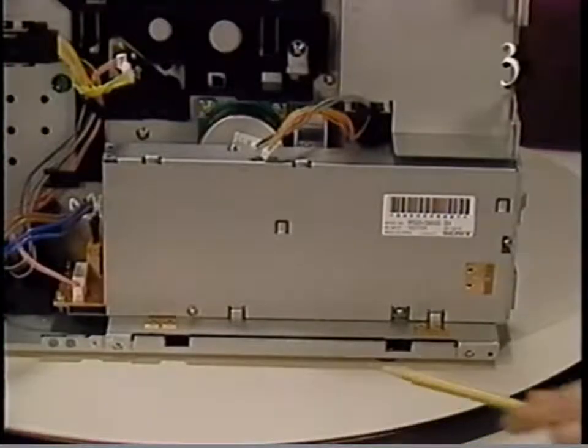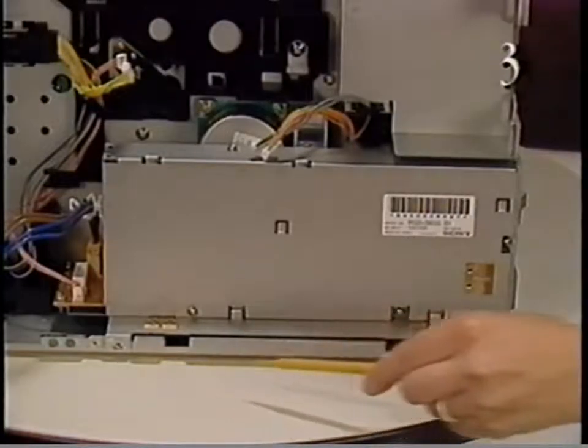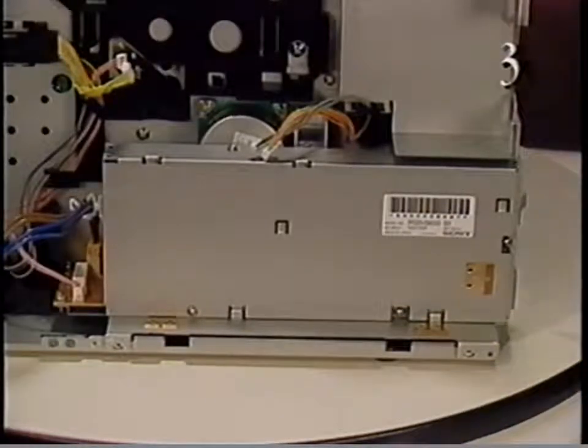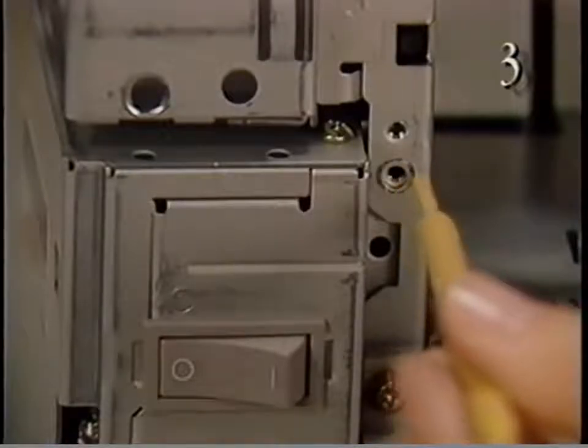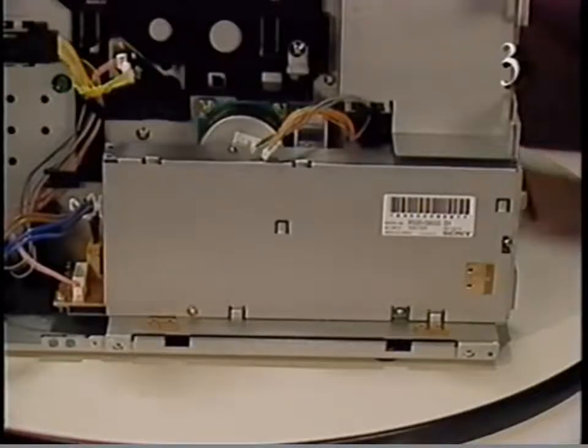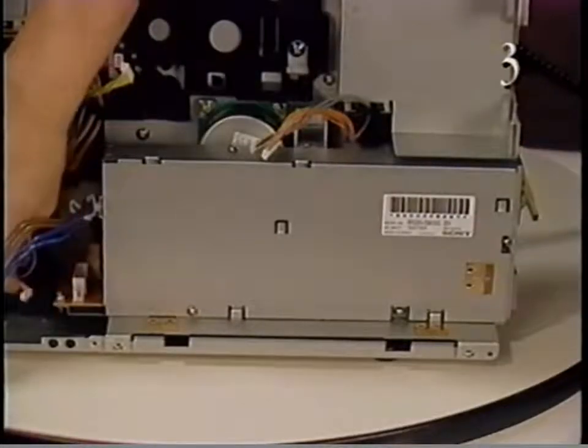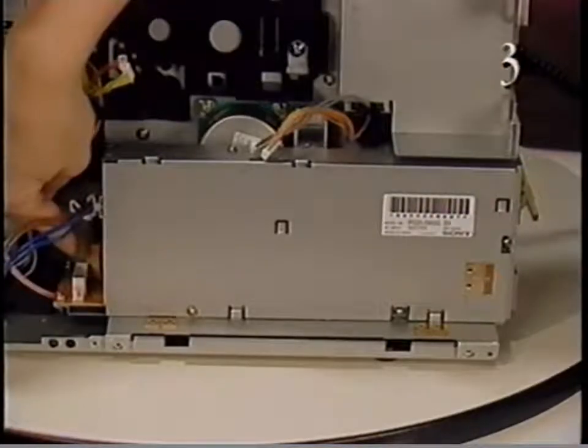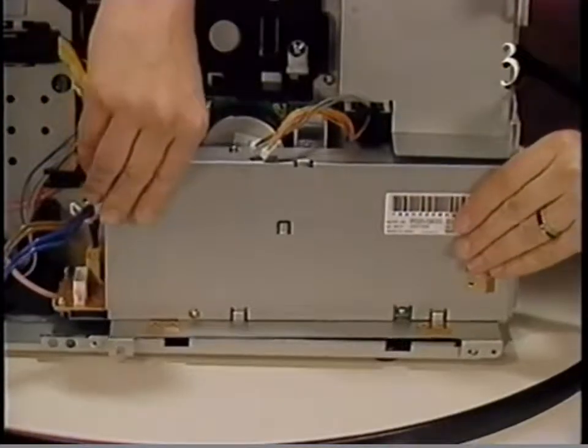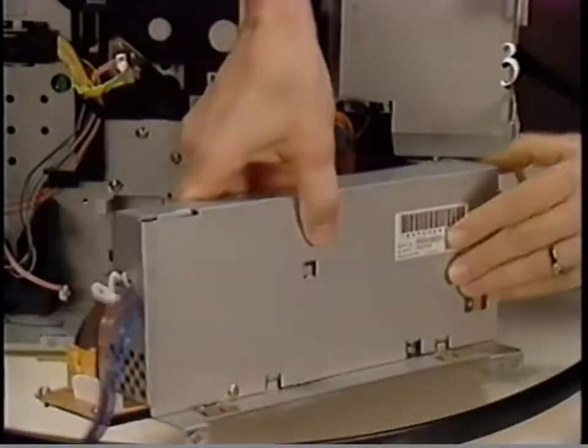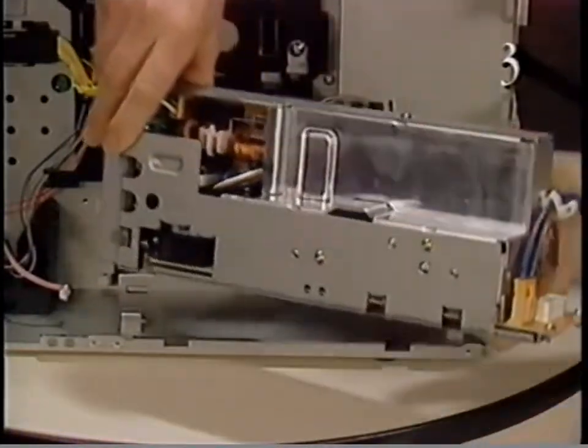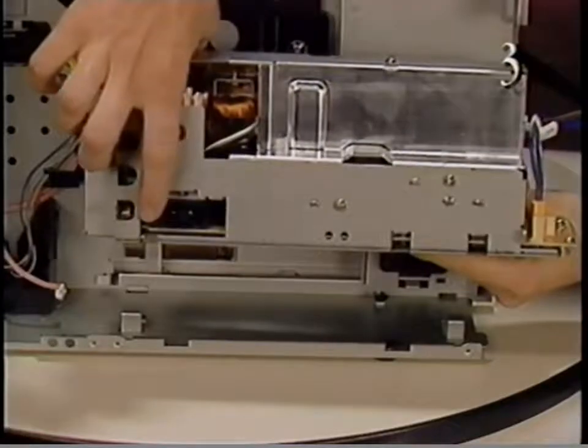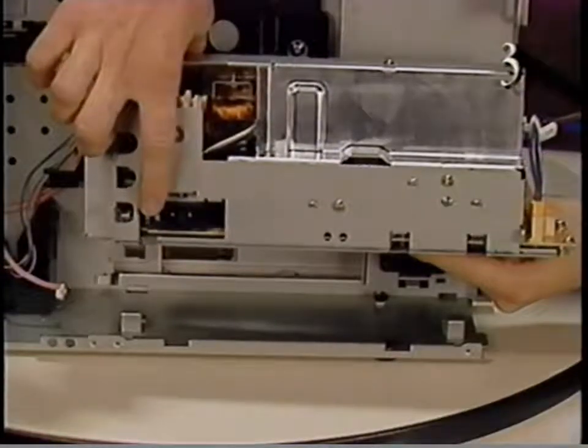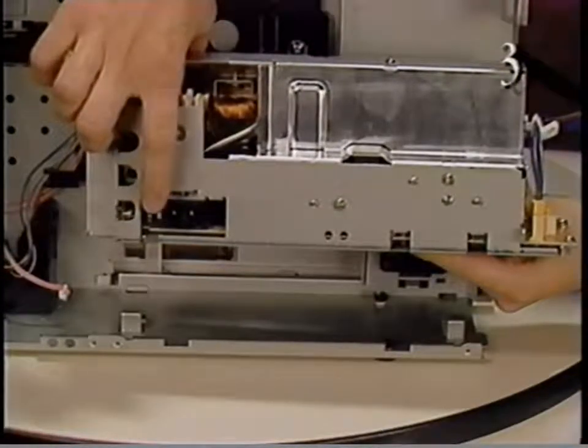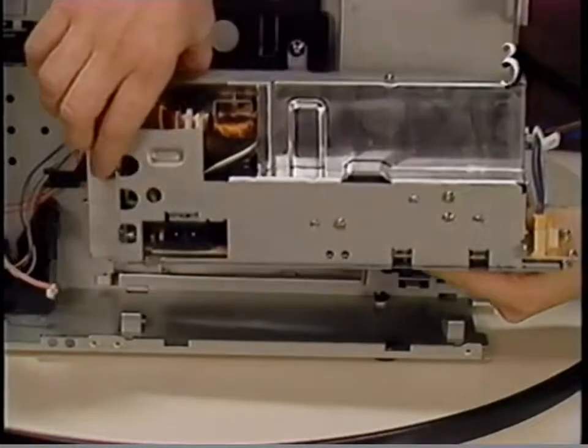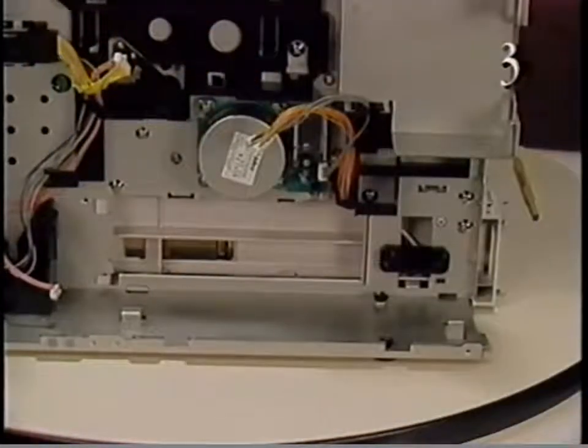Start removing the power supply by removing the 3 screws that secure the power supply to the rear chassis. Detach connector J104. Connector J103 should already be removed. Then pull out the power supply and remove it from the printer. There is a receptacle on the rear face of the power supply. It mates with the high-voltage connector block and may cause slight resistance when you're pulling out the power supply.